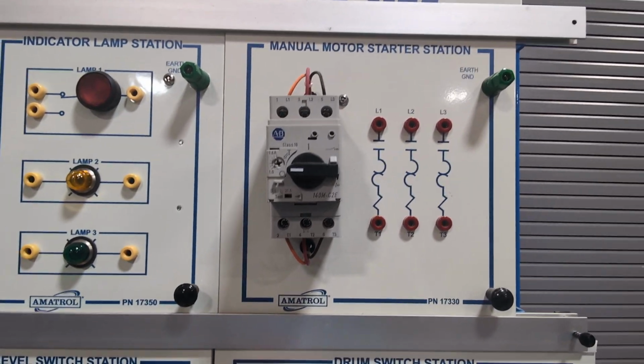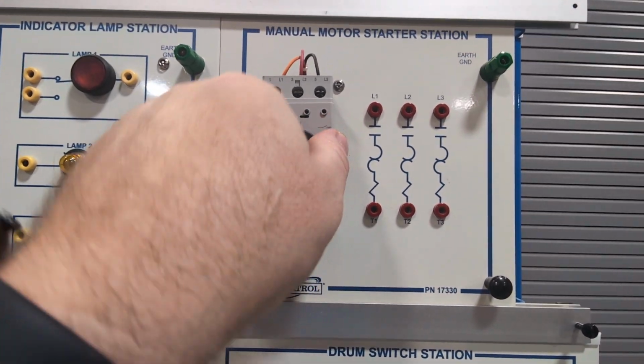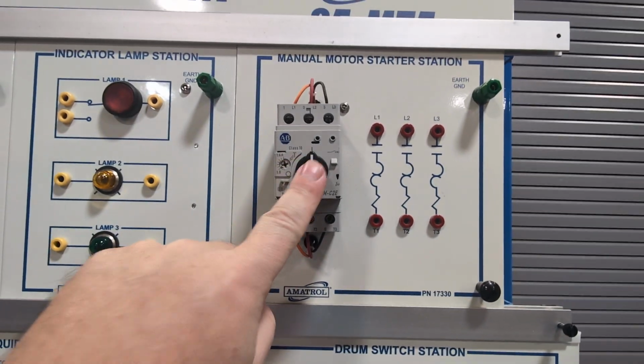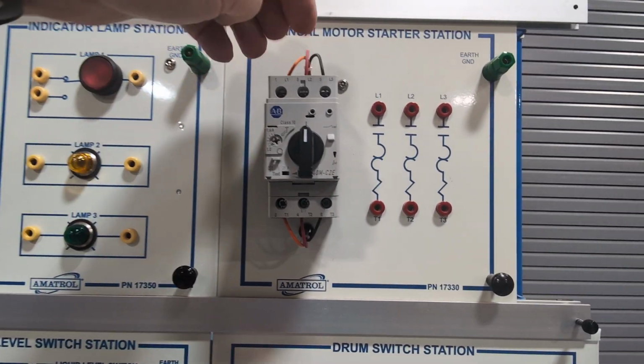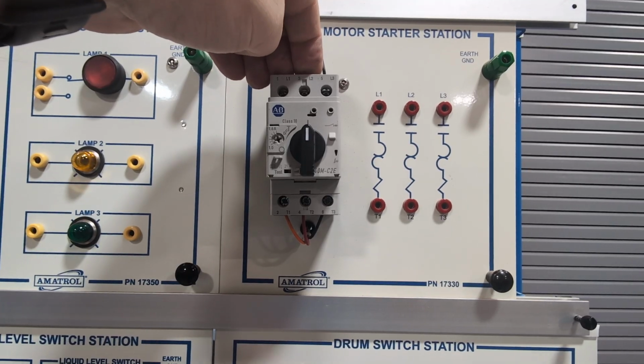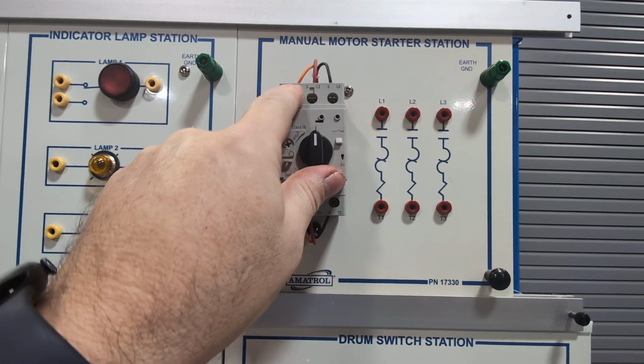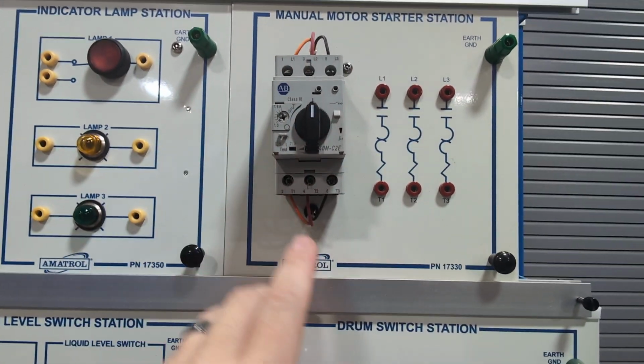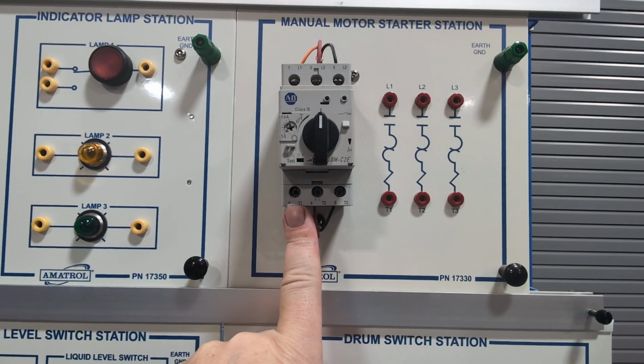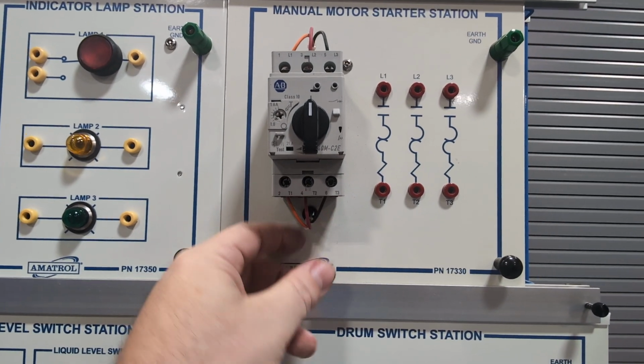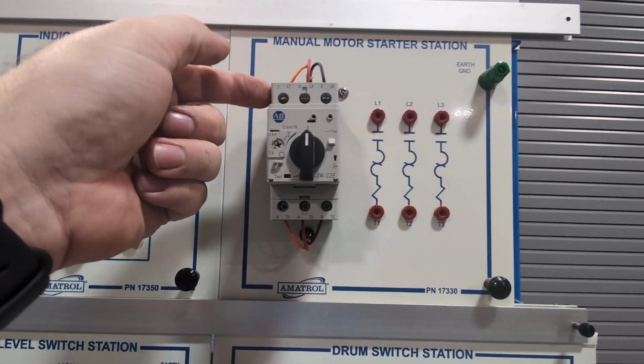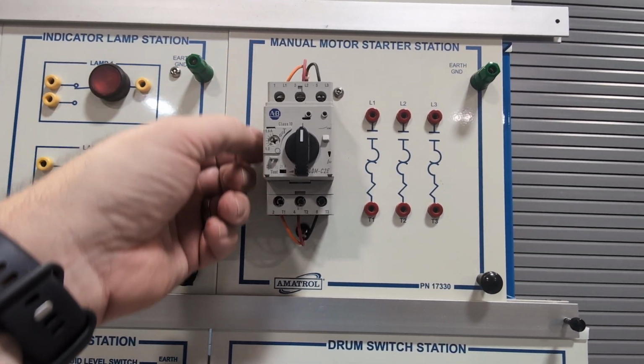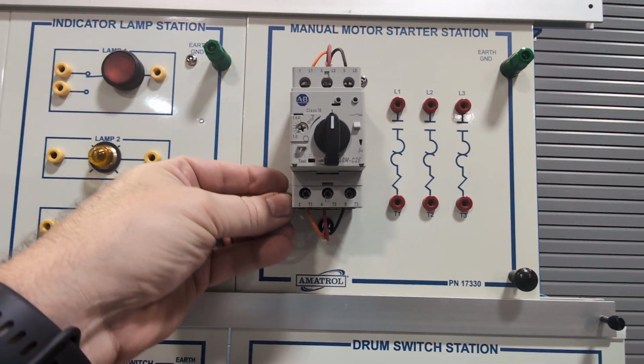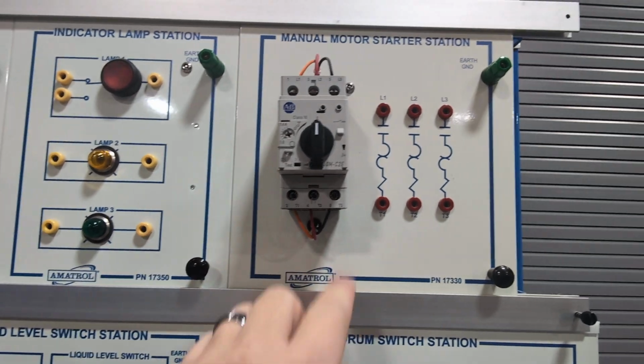This is a starter, a motor starter. They say manual because I can turn it on and off from here. My power in, your power always goes to the top. That's what L means. Line 1, line 2, line 3. And the bottom is your motor, T1, T2, T3. This goes to your motor. When you close it, this inside closes a switch, activating power through this side.